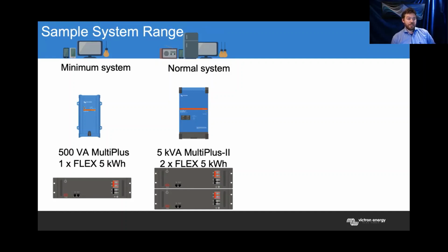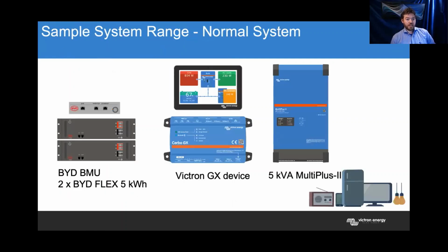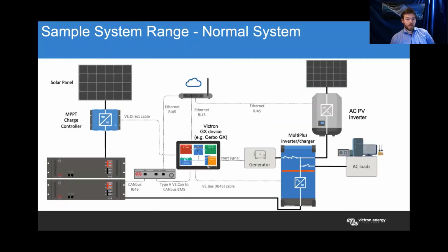But in some cases, depending on your system design, it may work that it'll supply the customer's load if they're not using the full capacity of the Multiplus 2. The surge capacity is 105 amps, which is great. Once again, very similar lineup, still requiring a GX device, and still requiring this time the single BMU for the 2 Flex batteries. Here's a slightly more complicated system wiring diagram, or a basic wiring diagram, to show this layout.